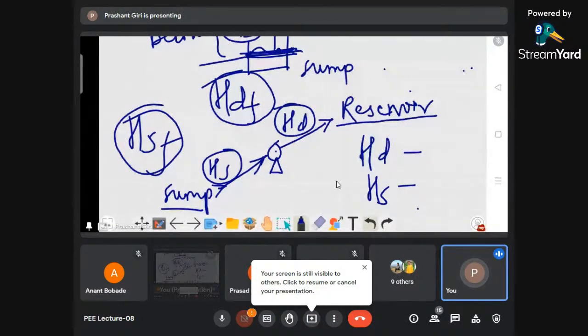लॉसेस जर वाढले तर पंपचं जेवढं आपल्याला डिस्चार्ज पाहिजे होता तेवढा मिळणार नाही, बरोबर. म्हणजे मला 10 मीटरला पंप करायचा आहे फ्लुइड, ते 10 मीटरवर जाणार नाही, कारण 1 मीटरचा हेड लॉस या फिटिंगने आणि पाईपने करून टाकलाय. म्हणजे 9 मीटर पर्यंतच फ्लुइड जाईल. Are you getting my point or not? It's very logical thinking if you know the basics behind it.